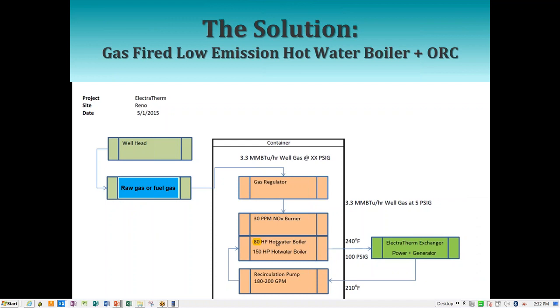We've got treated gas being used right now for this project, but this boiler is designed to use either one. Of course, it goes through a gas regulator. We're using the 30 part per million NOx burner, and you can walk down through the rest of that one line. Again, we're using a 150 horsepower hot water boiler, which is capable of generating twice the power that we're generating and consuming twice the gas we're using.